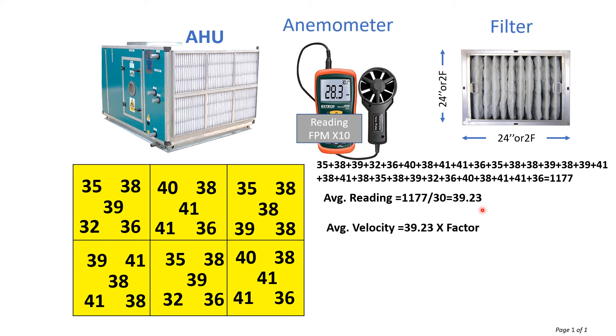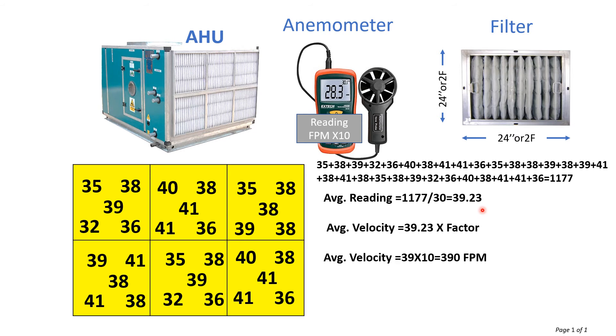For the average velocity, we need to multiply the average reading by the multiplying factor of the anemometer. The anemometer multiplying factor is 10, so the average velocity will be 390 FPM.